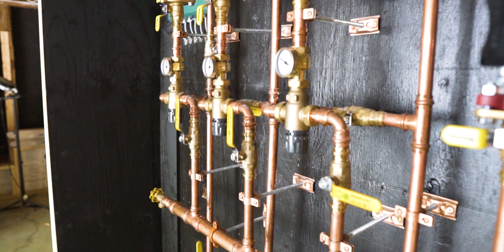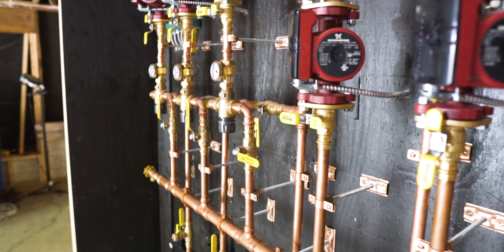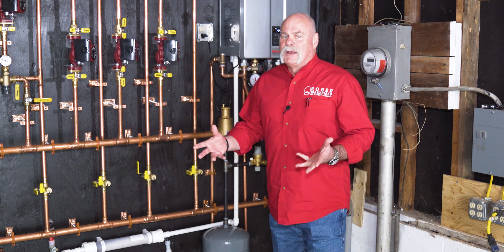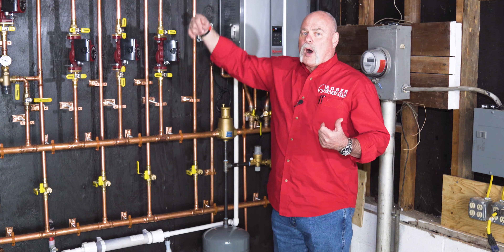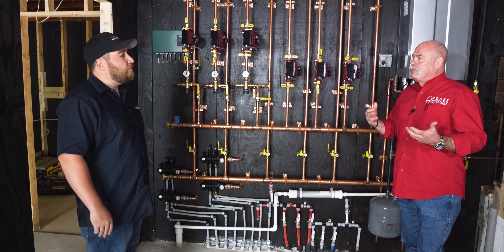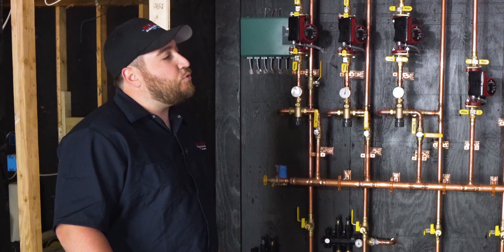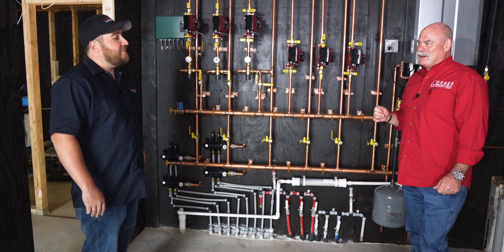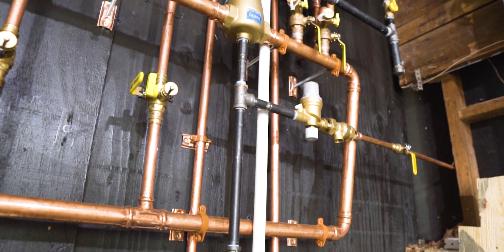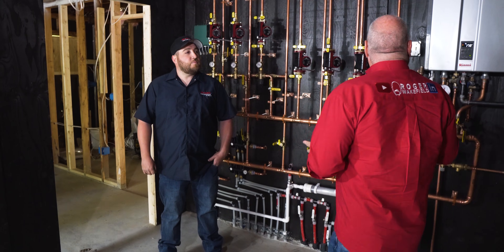This will not be just plain water in your heating loop system, will it? No. So what do you put in it instead? We'll add some antifreeze — about 30%. In Texas we don't even run water lines in the attic, we're starting to here lately because of PEX and expansion, but freeze problems can be a pain. The antifreeze will get down to negative 20 to negative 30 degrees. How cold has it gotten here? It's gotten colder. It will just gel up a little bit, slow down the flow. If it's going to get to negative 30 or 40, it's not going to stay at that for more than a couple of hours — it's usually in the middle of the night.